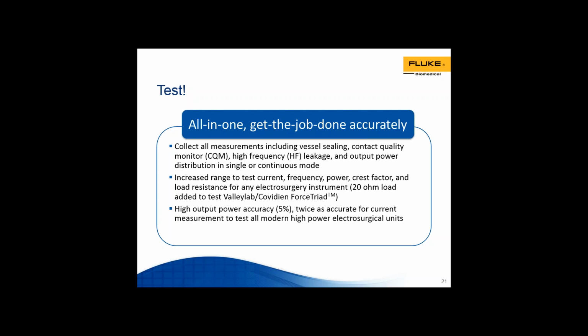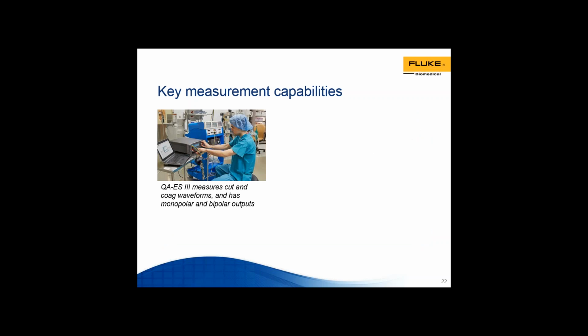The high output power accuracy for this product is 5%, which is twice as accurate for current measurement, and has the capability to test all modern high power electrosurgical units. So not only is the power accuracy industry leading, the current accuracy is also twice as improved to be able to offer you specs that you can rely on that give you quality results. And I had mentioned earlier that the product complies to IEC as well as ANSI and AAMI standards.